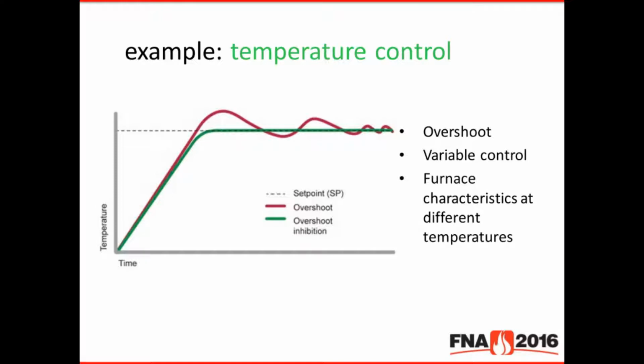But D does come in. D, the derivative, looks at the future. So if you have some kind of interruption in the process, maybe you've got a two-zone furnace with an inner door that opens and it's transferring from one chamber to another. The inner door opens, you get a sudden drop in temperature. If just the normal algorithm took over, you could be in a situation where the controller actually just wants to put in a lot more heat.